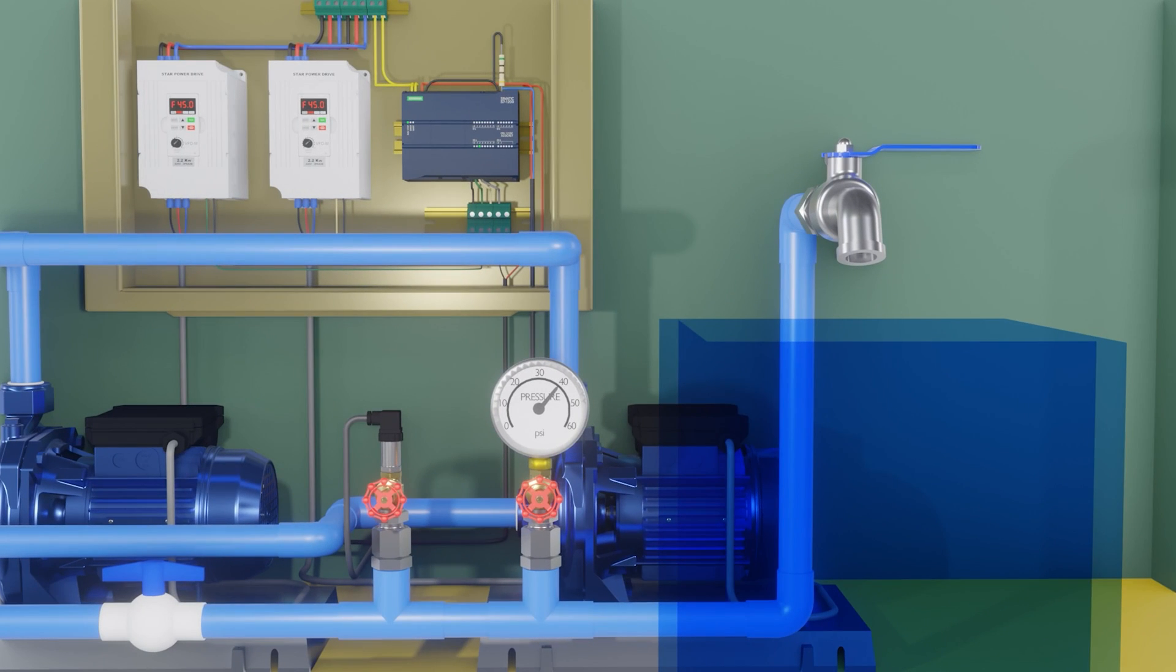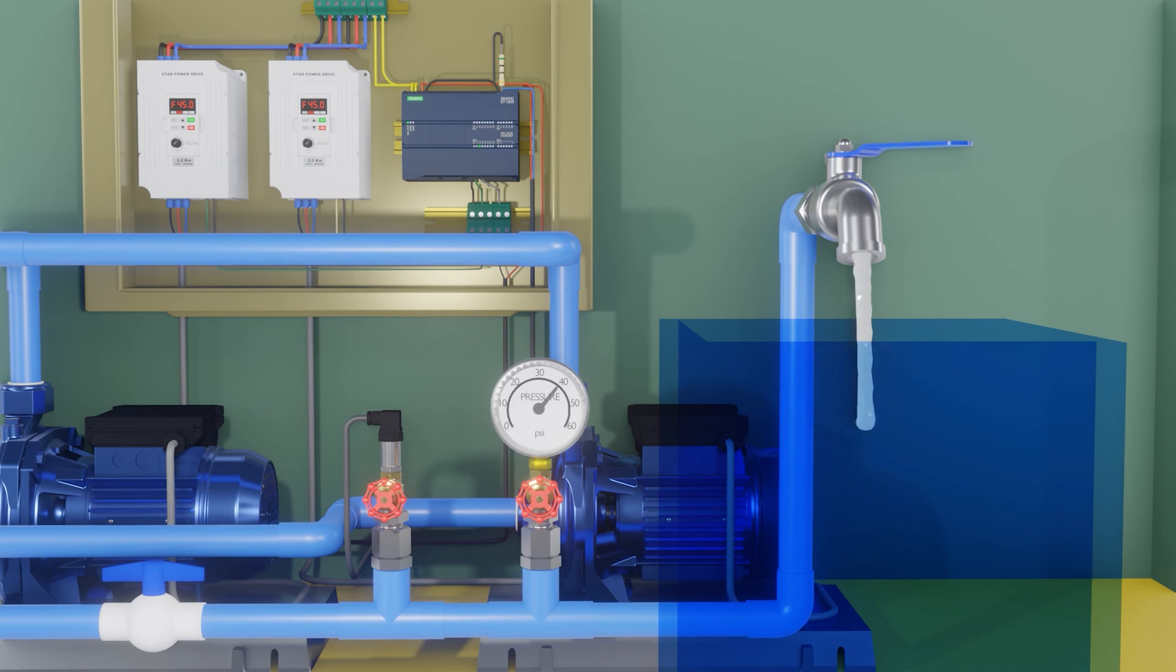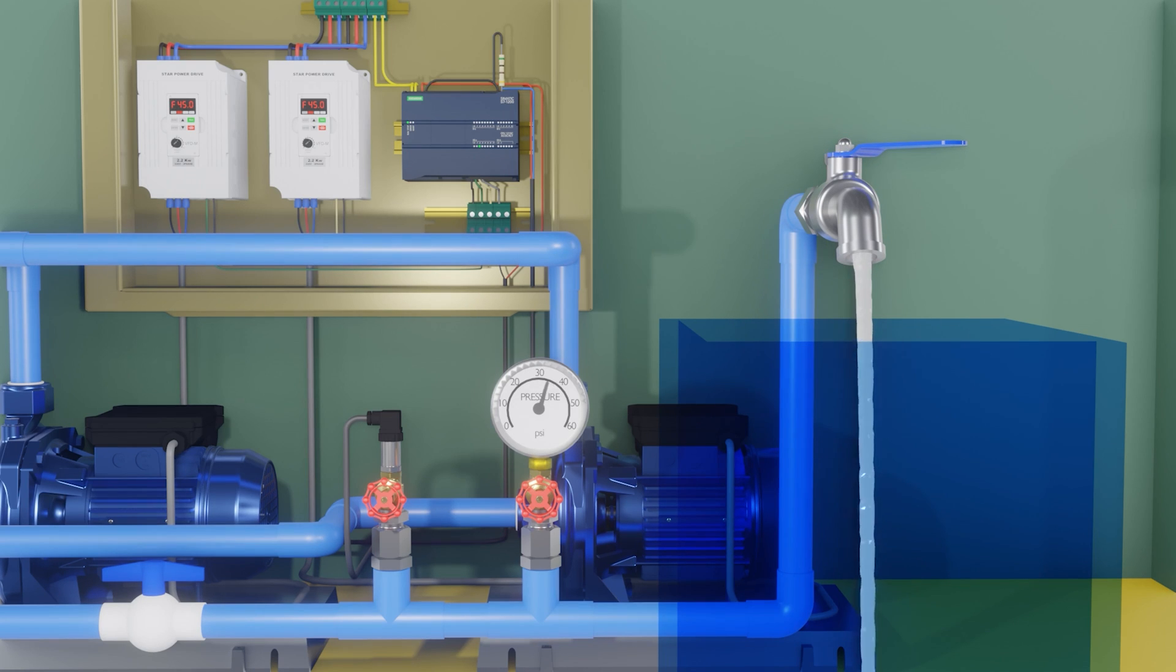Let's open the tap halfway. The pressure begins to drop. When it is less than 30 PSI activate frequency drive 1. The pressure rises until it exceeds 40 PSI. And frequency drive 1 turns off.